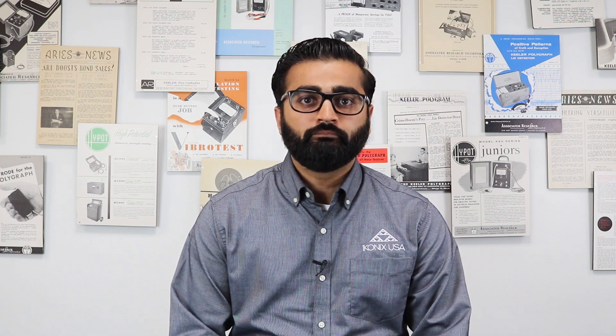According to IEC 60601-1 standard, touch current is defined as current that flows from an enclosure of an electrical device to earth via an external path. Current can also flow from one enclosure point to another enclosure point. Touch current is designed to measure the current that a human body would be exposed to in the event of a fault occurring within an electrical device. In order to measure touch current, the measuring device labeled MD in this image needs to be in a proper position. As seen in this image, the MD makes contact with an enclosure point while standing on earth ground.